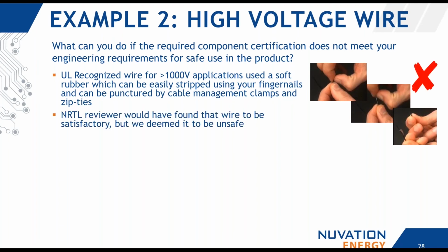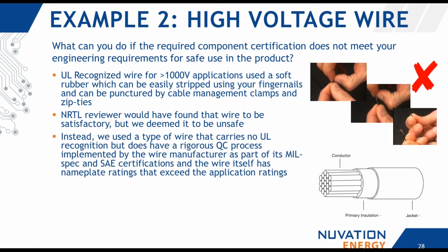So the interesting part here is that wire technically has UL recognition. So an NRTL reviewer would have found that wire to be satisfactory. But we require a wire that doesn't do that. So it's deemed to be unsafe, and this is by the engineering team, not by the NRTL. And so you get into a position where we need to have a wire that doesn't do that. And the wire that we were able to find, or the engineering team would like to use, doesn't have a UL recognition, but it does have rigorous QC processes implemented by the wiring manufacturer because it is a mil spec and SAE spec cable. And the wire itself has nameplate ratings that far exceed what you'd find in stationary storage. We're talking about wire that can be used in fighter jets or marine applications. And if we're going to be using it in a stationary storage system and in a UPS building somewhere, it's not under the same sort of strain that cable was designed for.